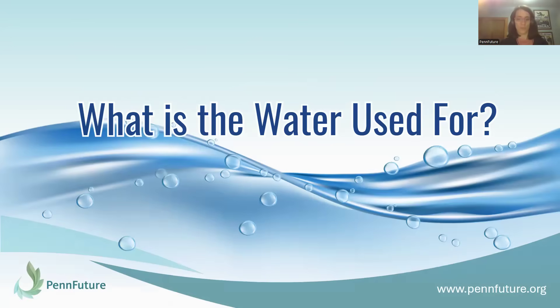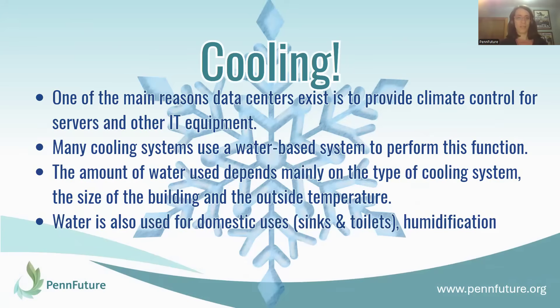So what is the water used for? For the most part, it is cooling. One of the main reasons data centers exist is to provide climate control for servers and other IT equipment, and many cooling systems use a water-based system to perform this function. The amount of water used depends mainly on the type of cooling system, the size of the building, and the outside temperature. Water can also be used for domestic uses such as sinks and toilets and humidification. However, if you are using a water-based cooling system, that will be the overwhelming majority of the water used in a data center.